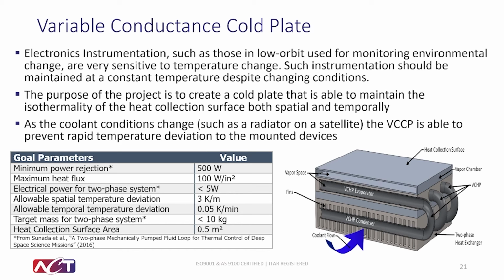Therefore, the purpose of this project was to create a cold plate that can maintain isothermality of the heat collection surface, where these electronics are mounted, both spatially and temporally. As cooling conditions change, such as on a radiator or on a satellite, or as the heat load of the electronics changes, the VCCP, variable conductance cold plate, is able to prevent rapid temperature deviation of the mounted devices.